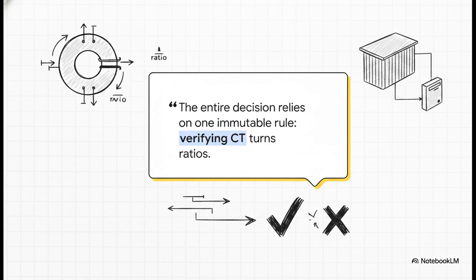Well, the entire decision relies on one immutable rule: verifying CT turns ratios. You absolutely must verify your CT ratios first, every single time. This one piece of data dictates your entire engineering path forward. If you get this wrong, there's no way you'll be able to properly commission the REF scheme.